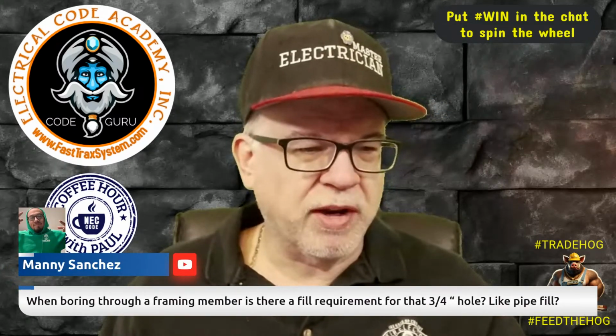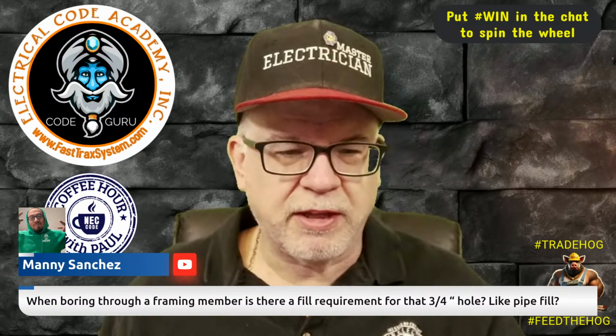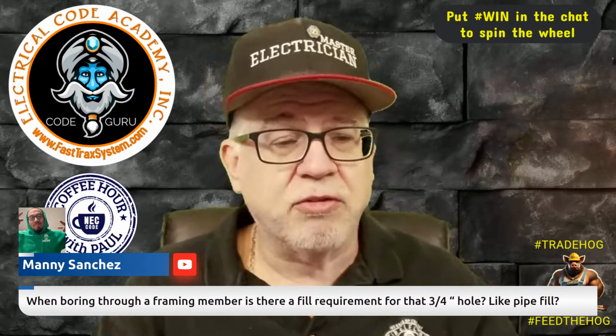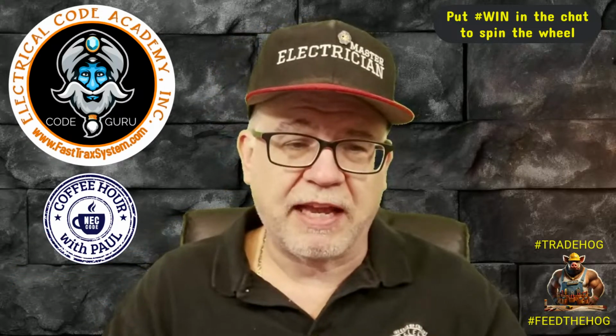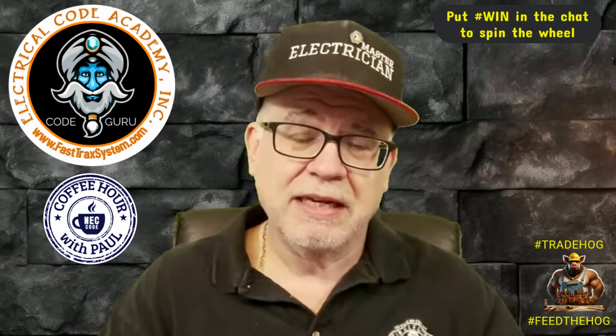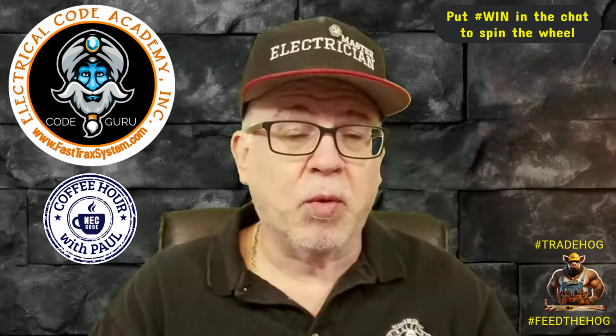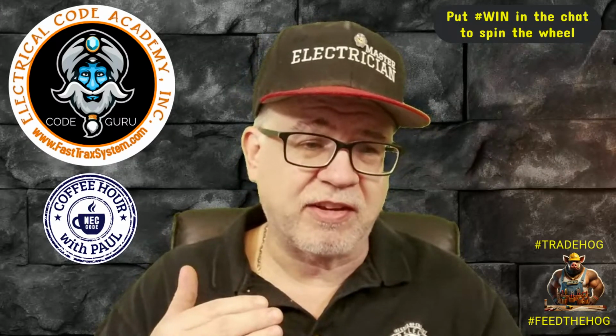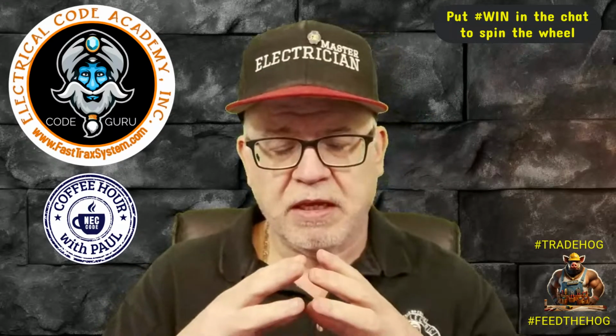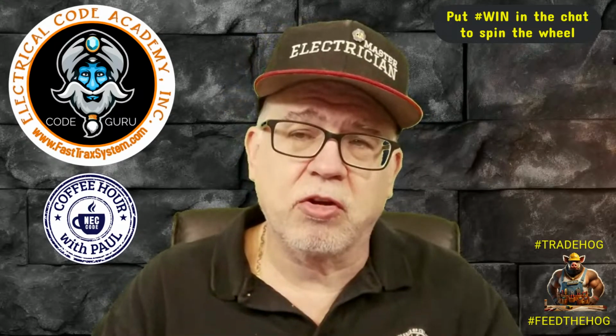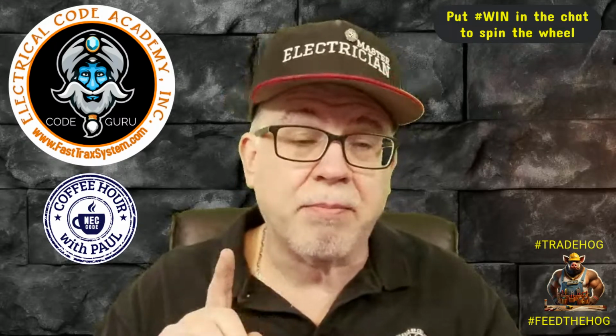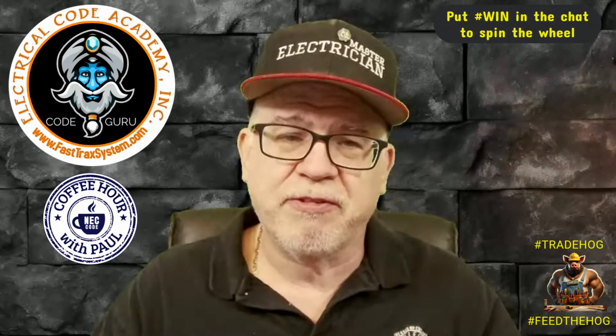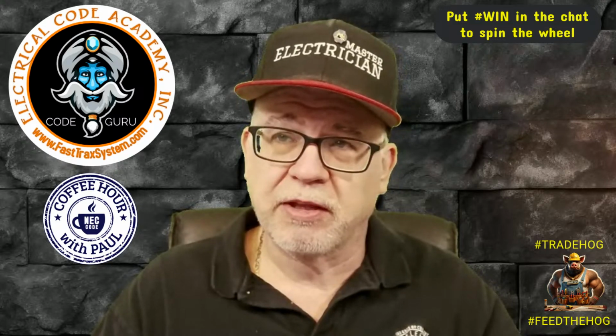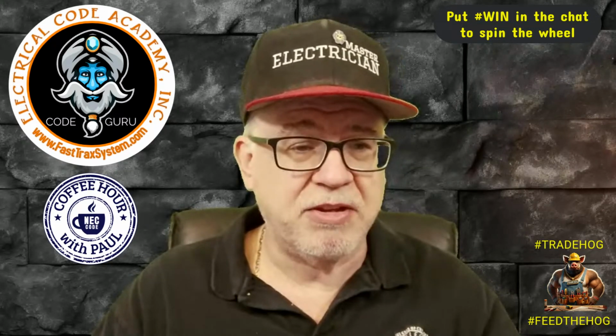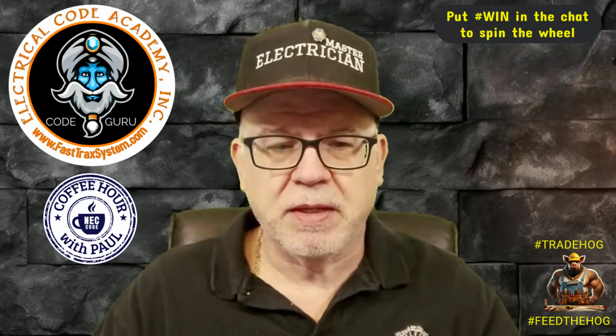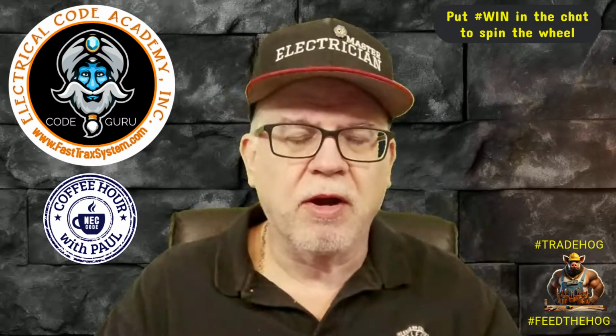Let's see here. When boring through framing members, is there a fill requirement for a 3/4 hole like pipe fill? No, there isn't. I do get that question a lot, Manny. A lot of people ask how many NM cables they can stick through a bored hole. The reality is, if it's a bored hole that's not going to have insulation in it, it's not going to really affect anything. But if we're just talking fill, you can put as many cables through the bored hole as can fit without damaging the cable. If putting them through causes the sheathing to rip or get damaged, then that's a problem. But there is no fill. It's not a raceway, so there is no fill requirement.